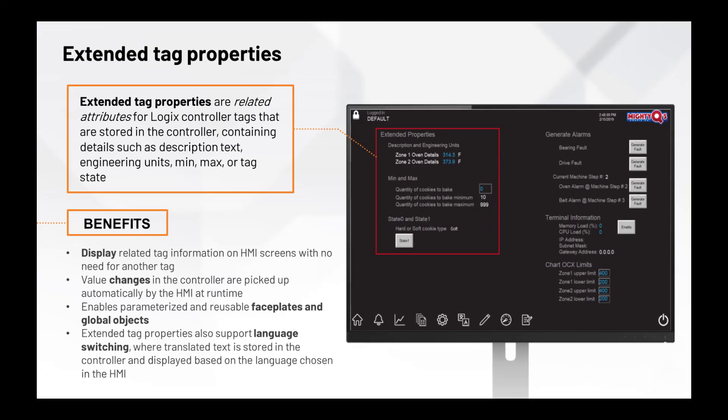ControlLogix Extended Tag Property Values are attributes of a tag contained within a Logix controller that can easily be displayed on HMI screens, whether using FactoryTalk View Machine Edition or FactoryTalk View Site Edition. Support for Extended Tag Properties began with FactoryTalk View Machine Edition version 9.0. Within a Machine Edition application, tags can be assigned to specific extended tag properties in the controller. Extended property values can be modified in the controller and the running Machine Edition application is automatically updated. There is no need to rebuild the runtime application, thus saving time during development.